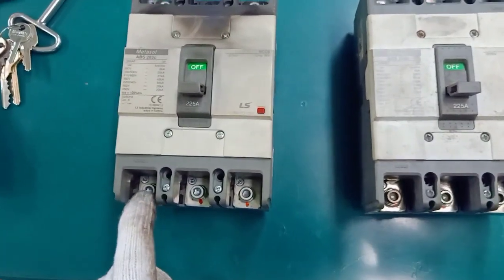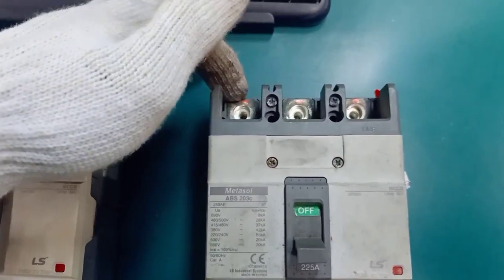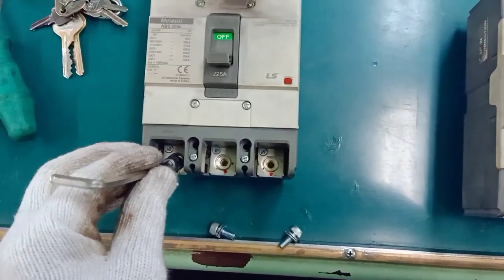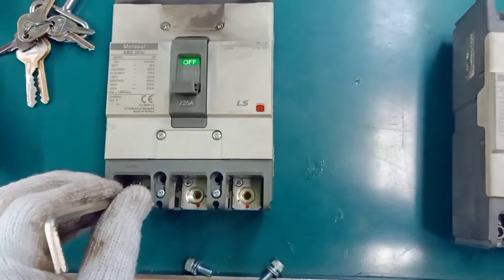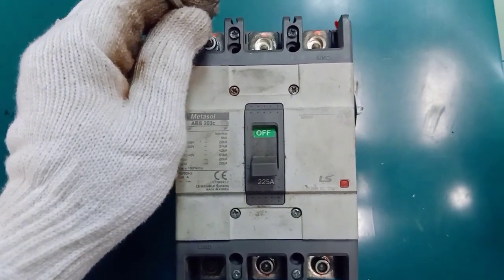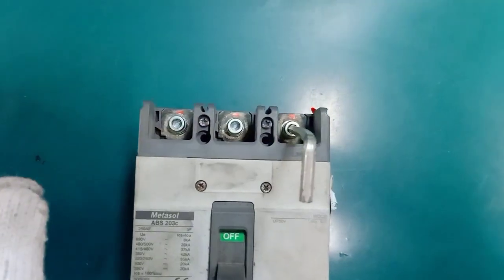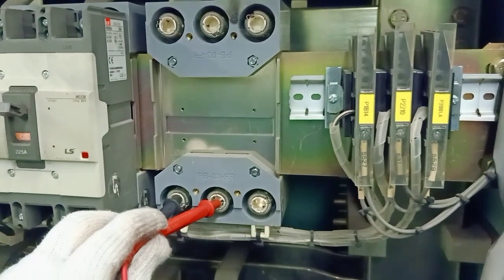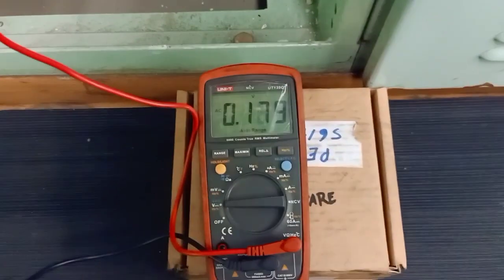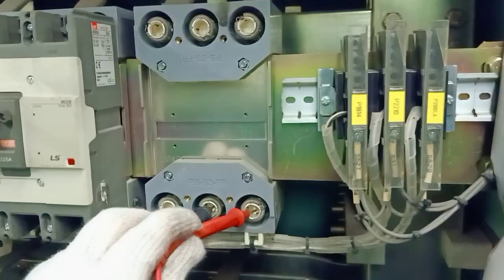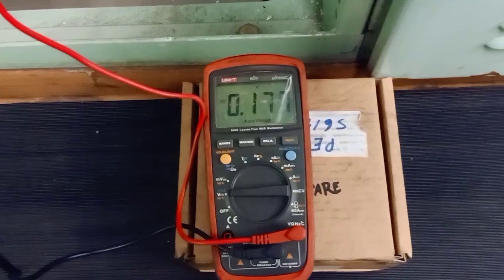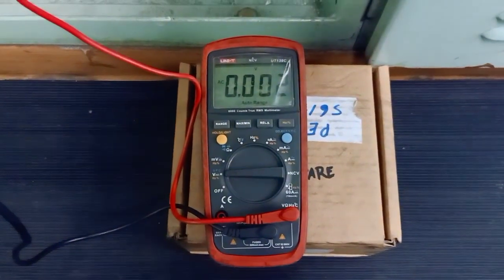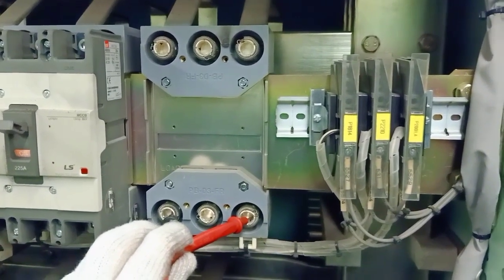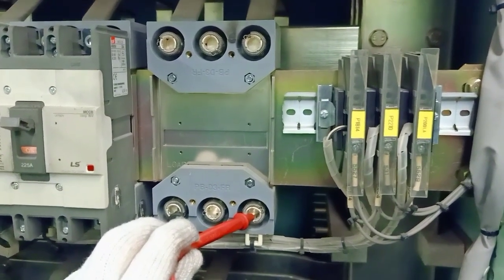Now I'm going to get this Allen wrench bolt and transfer it here. So remove these 3 Allen screws and transfer them to the new circuit breaker. Connected now all the Allen screws. Check once again the load side voltage. It is 0, so it's normal. Next, 0, it's normal. Next, the last one, it's normal. Now ready to connect the new circuit breaker.